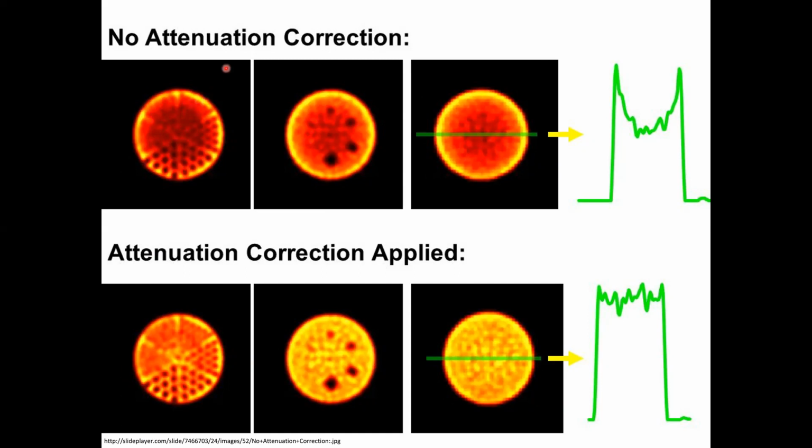And so when you're creating nuclear medicine scans, when you look at your raw data, if I had a uniform activity, uniform X-ray or gamma ray emission as a function of space in here, other than these holes that are drilled in this phantom, the picture you would get without any correction looks something like this, right? And it's really bright on the edges, darker in the middle. But this is all due to the probability of absorption of those gamma rays by the patient.